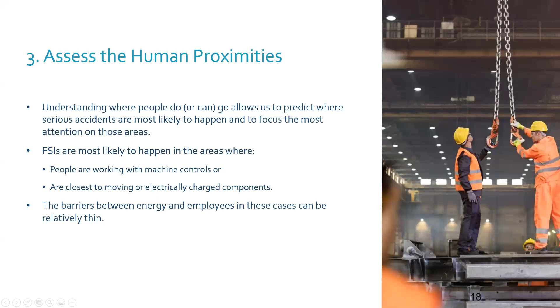Modes of failure. This is one that sort of comes with time and just seeing a lot of different failures. Quick story, kind of a fun one. I walked a client site that had a lot of conveyance, a lot of different conveyors running through the different rooms within this building, and the conveyance was run with a slew of 480 electrical motors, right? Just like most of industry. Some were mounted in a way where the motor was allowed to vibrate, had a little bit of travel, and over time, the conduit bodies that were feeding the wiring into these motors would shake loose and come off.